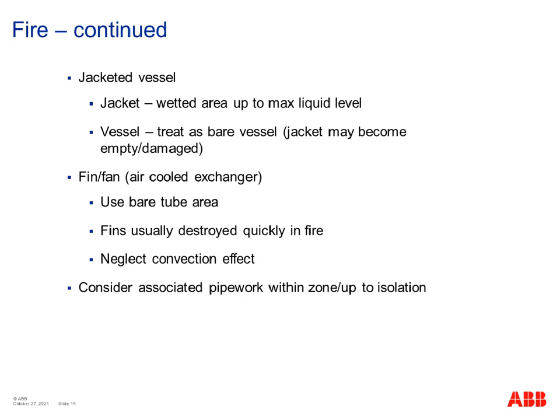relief device. If you're thinking about the vessel underneath the jacket, then you'll have a different approach, and you'll think about the bare vessel, because the jacket could actually, in the event of the fire, fail, it could empty of the liquid or whatever material is in the jacket, so you lose the protection there, or the jacket may just be badly damaged by the fire and may just fall off the vessel, leaving the vessel bare. So in each of those scenarios, you're thinking about what's the worst case.